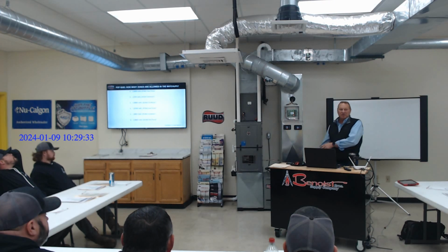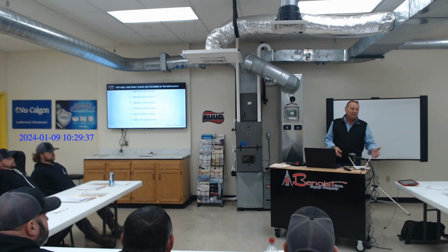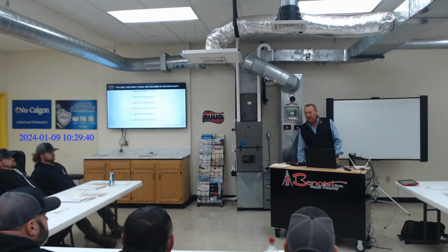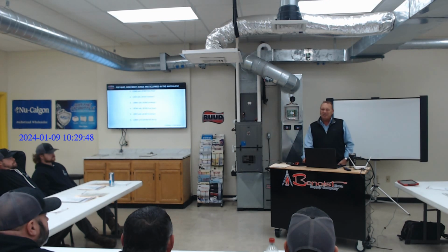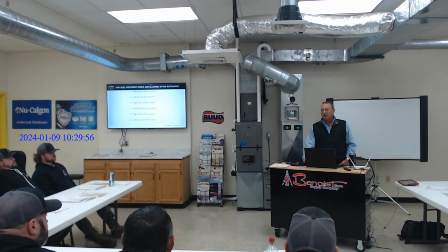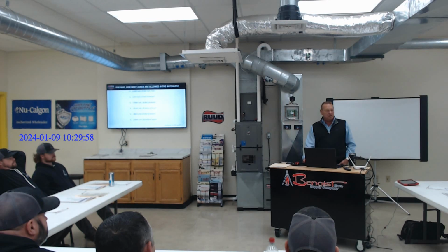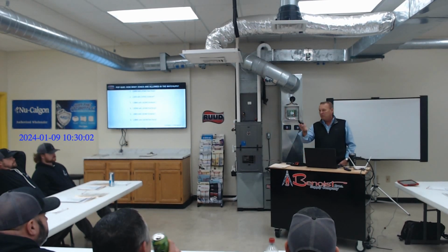That's why everything's oversized. Or it's oversized because guys used to keep floor plans, and they didn't have a 70, they put 100 in, they upgraded it. And I get the argument, well, the customer doesn't want to downsize. Well then guys, I don't care what the customer wants. The customer doesn't know their duct system. It's your headache once you put it in. So if you aren't sizing it right and the customer says, no, I want a 115 furnace, and you just throw it in because that's what the customer wanted, and it's too big, we can't fix that.